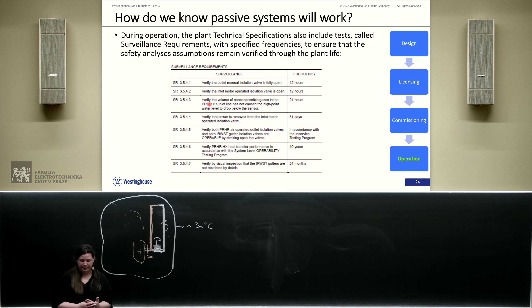So, in conclusion, what we've tried to convey to you is that AP1000 really has a different approach to safety compared to all other operating plants. We've kept the active systems, but simplified them — they are non-safety related, meaning we do not rely on them to maintain the plant safe. And we've added that robust line of defense made up of the passive safety systems. Compared to any other plant, AP1000 has a unique, unparalleled response to an extreme event, because we are self-actuating — our passive safety systems will always actuate. We're self-sufficient, providing an extended grace period and extended mitigation time without operator action. And we are self-contained: because of the compact footprint of the safety systems, we can place them where they're protected against flood, seismic events, or any external hazards.